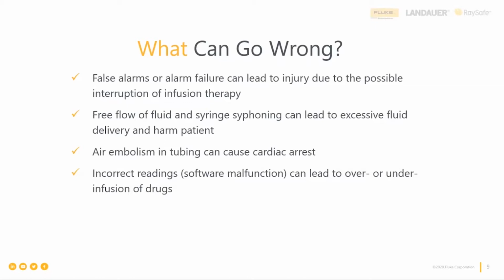So we want to be very, very careful about air embolism. It is a deadly problem, so we want to make sure that that is not happening. Incorrect readings can always happen, and that's another reason why we test and run all the infusion pumps through their paces with some sort of measurement system that allows us to evaluate whether the function of the infusion pump is working properly in accordance with the manufacturer's specifications.